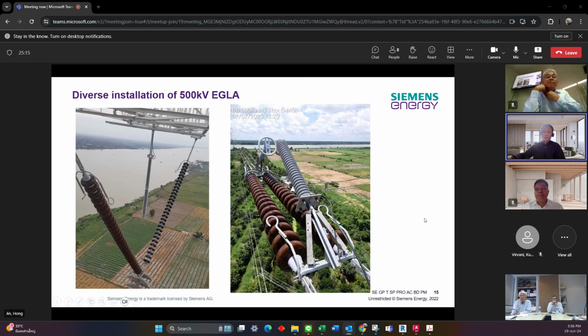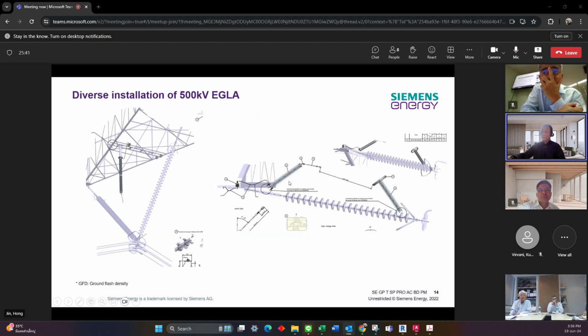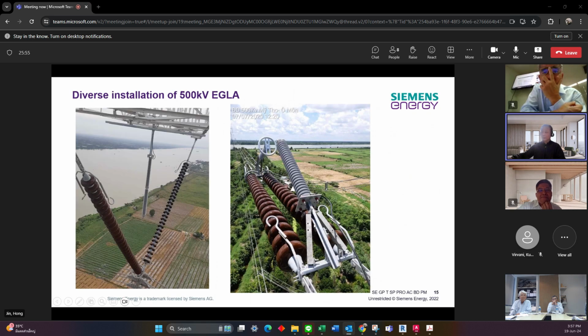So this is the picture taken from a Vietnam transmission line after installation. This is the V string, and the surge arrester can be installed at the middle. And this is the electrode, and on the other side is the high voltage electrode here, like the corona ring. And this one is on the tension strings. If we go back to the drawings, on the last picture, you will see this is a tension string. And we can use the adapter to install the surge arrester on both sides, on the hardware of the insulator strings. Here, you see, this is the bracket provided by the local EPC. And then we have a platform to install the surge arrester on the tension insulator.